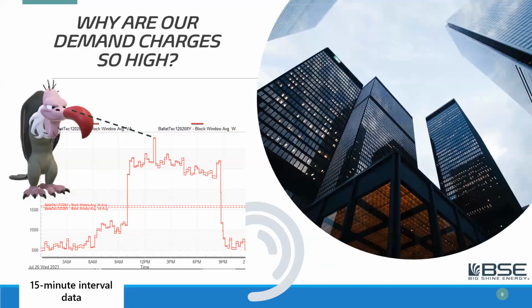So today, there's all kinds of things that we're under pressure with, and we want to be able to optimize our operations. For example, demand charges. Every 15 minutes, the utility will typically monitor our kilowatt demand, how many kilowatts we're drawing, and then that one interval per month that hit the peak will be charged a cost based on that, and that'll be added to our consumption.